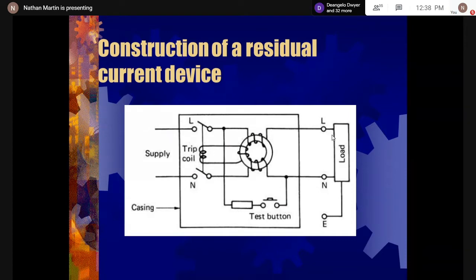So now you have a node develop. All of you do circuit analysis. If we have a leakage current, at that point we have a node, meaning the majority of the current is going to flow to earth, and some current is going to flow back to the neutral. We learn the theory, and we'll see how the theory applies. Now, the current entering the core from the line and the current entering from the neutral, which is the return current, will be of different magnitude, correct?